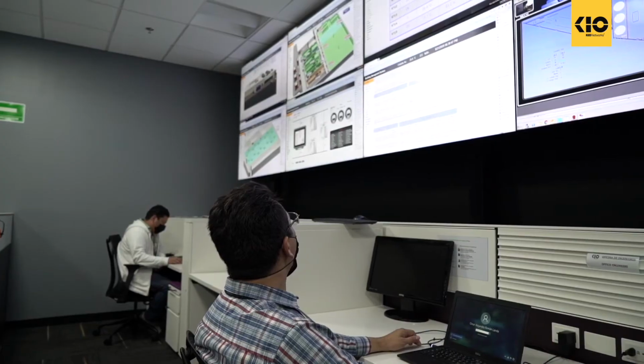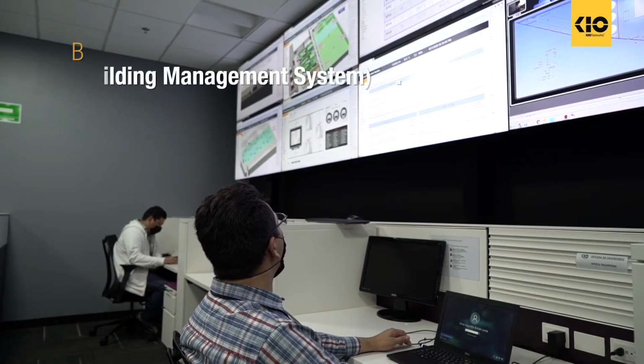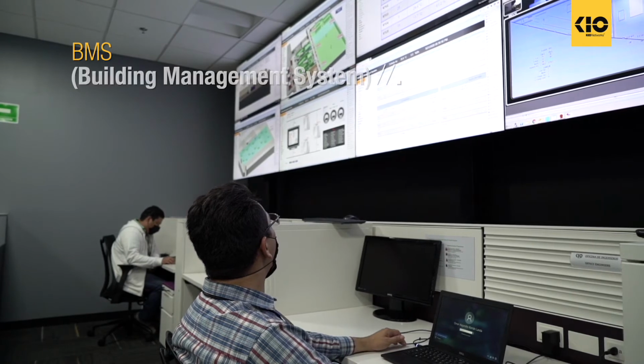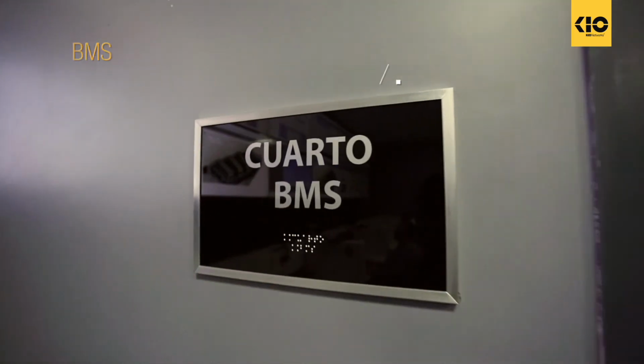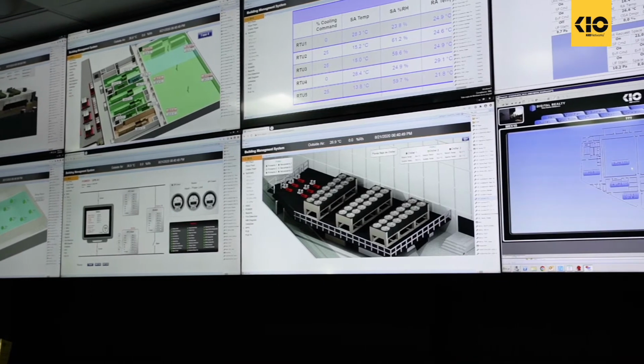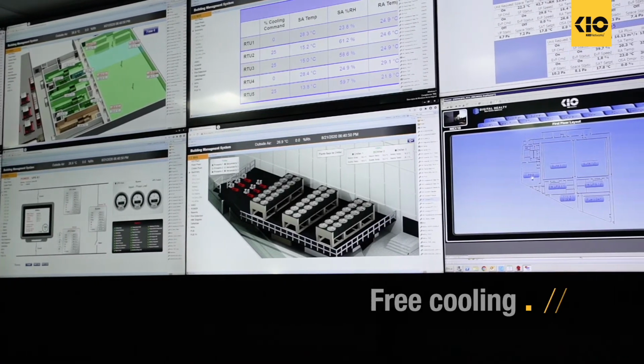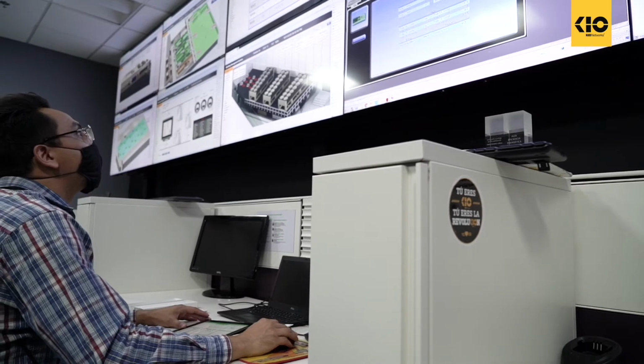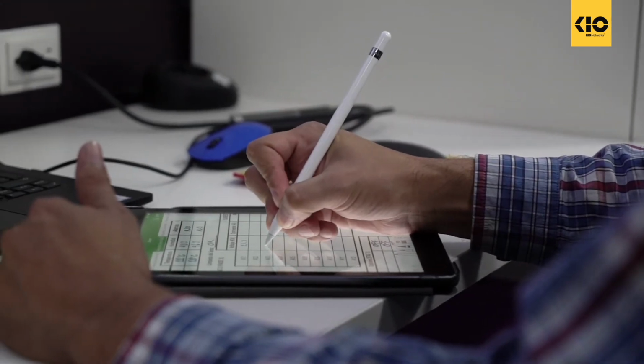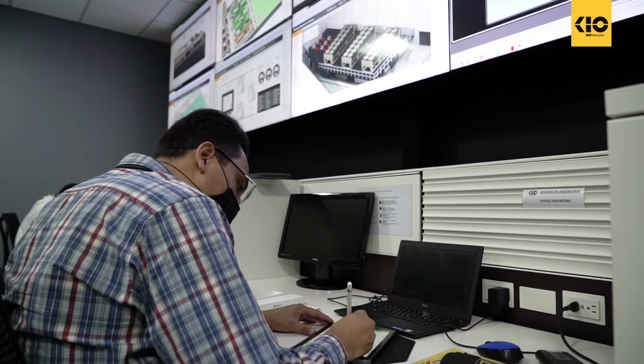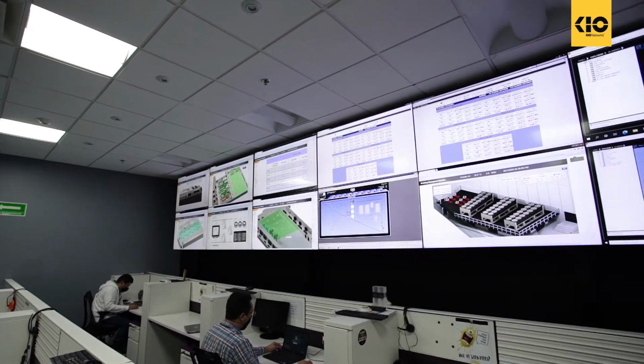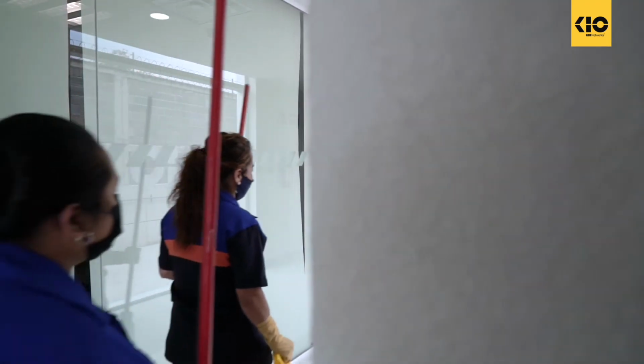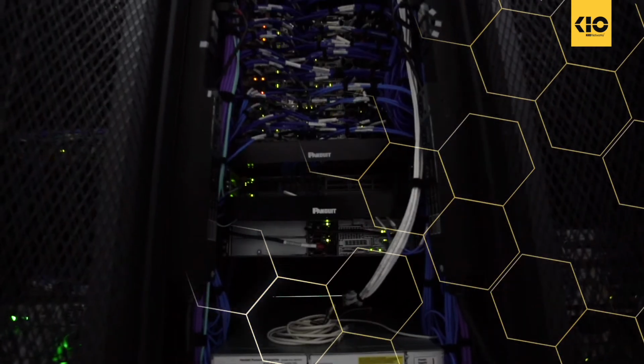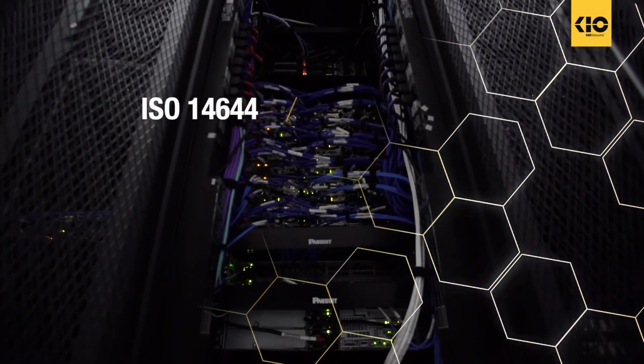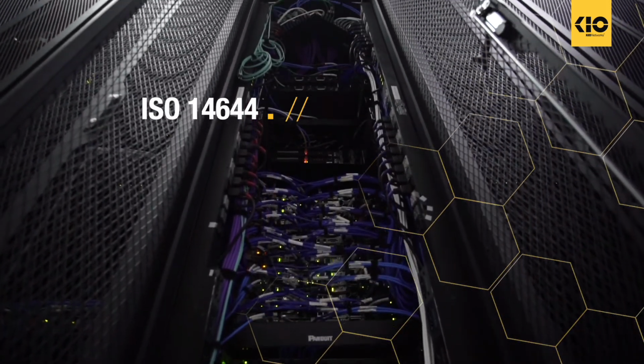The correct operation of a cooling system is monitored by the building management system and operation engineers who are on site 24/7. The BMS system notifies the operating conditions of temperature, humidity, pressure, and percentage use of free cooling. It also monitors the operating conditions of the electrical infrastructure to maintain air quality, in addition to the changes of MERV filters in the different layers. Specialized personnel carry out 2 thorough annual cleanings using vacuum cleaners with HEPA filters, verifying compliance with the parameters of ISO 14644 for clean rooms.